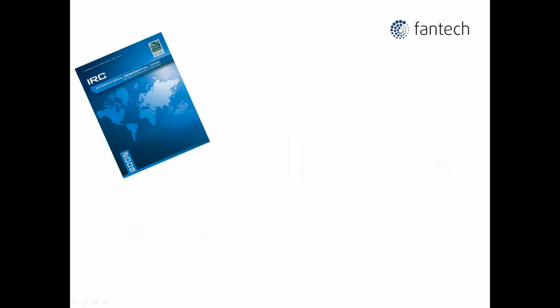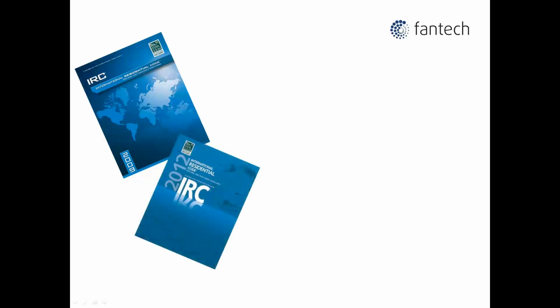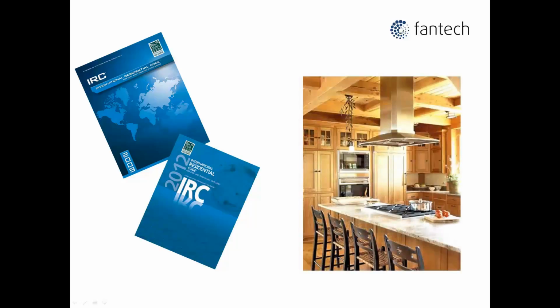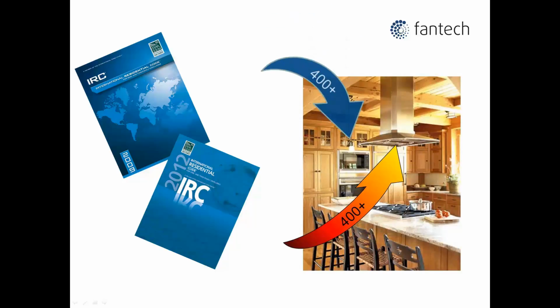The 2009 and 2012 versions of the International Residential Code recognize the need for makeup air for kitchen exhaust fans over 400 CFM and the requirement to supply air at the same rate as the exhaust air, with a closure to stop air infiltration or treated air leaking out.